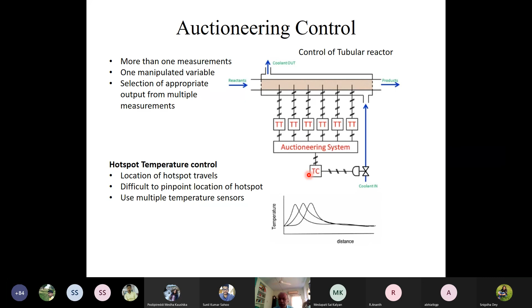Now for this selection of the appropriate output from the multiple measurements, we use a selector switch. The selector switch can be a low selector switch, a high selector switch, or a median selector switch. In this example, obviously we'll take the high selector switch, which basically gives me the highest temperature, and based on this high selector switch we get the hotspot temperature, and accordingly we control the reactor temperature. So this is basically called the auctioneering control, or selector control based on the selector switch.